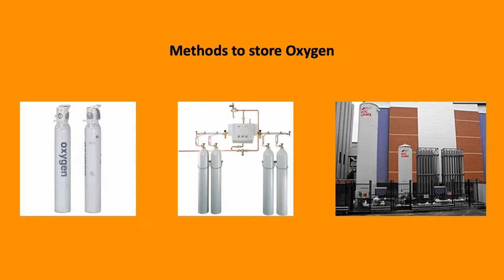It can be stored in cylinders of varying sizes C, D, E or F at 137 bar, or they could be joined together in a cylinder manifold for one common outlet. And finally it can be stored in a VIE, vacuum insulated evaporator.